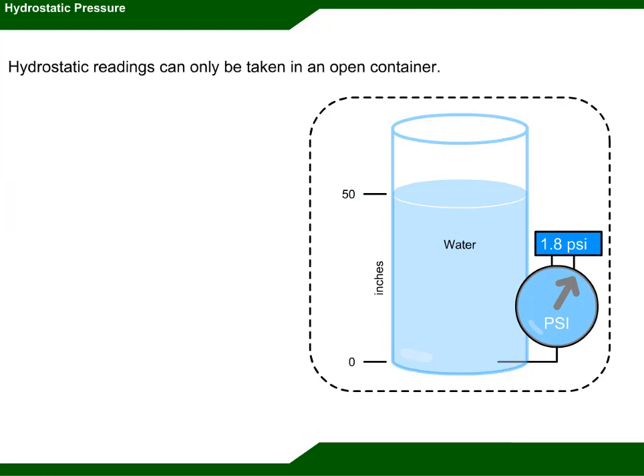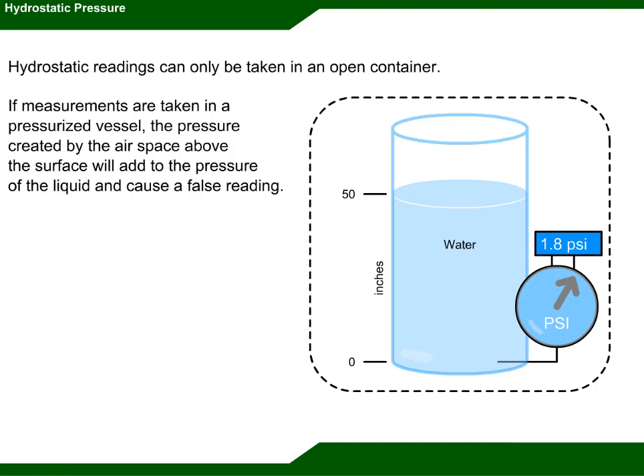Hydrostatic readings can only be taken in an open container. If measurements are taken in a pressurized vessel, the pressure created by the air space above the surface will add to the pressure of the liquid and cause a false reading.